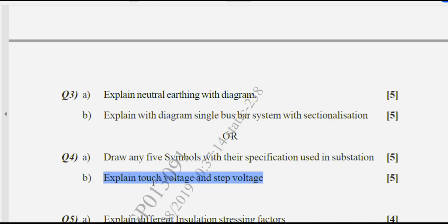Beside that particular point, a circumference of potential gradient is going to develop, of, let's say, 9 kilovolt, 8 kilovolt, 7 kilovolt, 6 kilovolt, and so on. Whenever a person enters that potential gradient area or zone, one foot is in, say, the 8 kilovolt area, and the other foot is in the 7 kilovolt area.